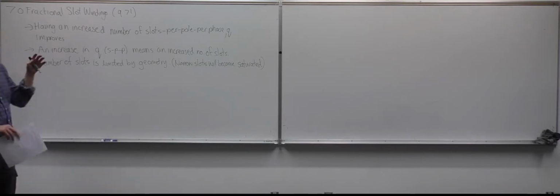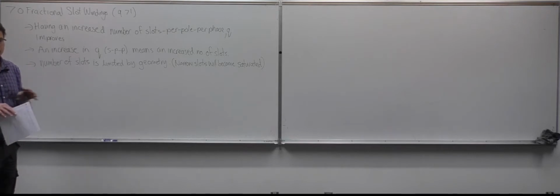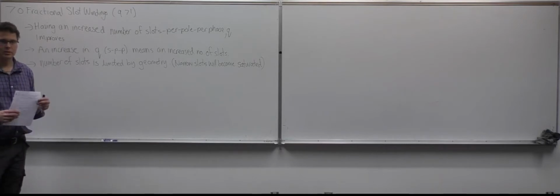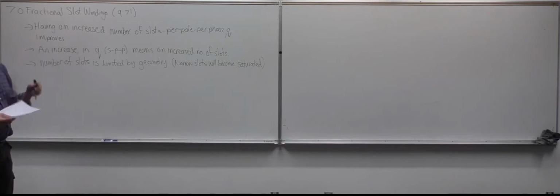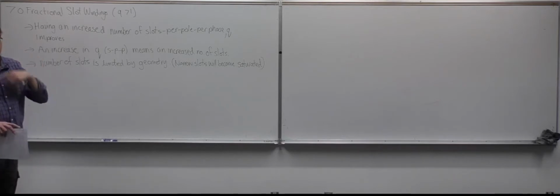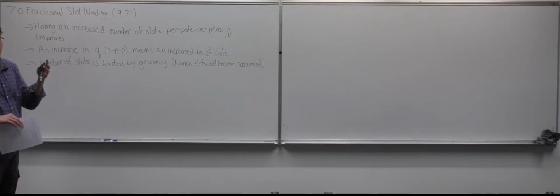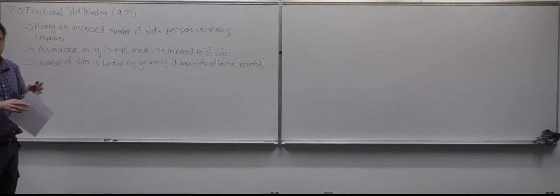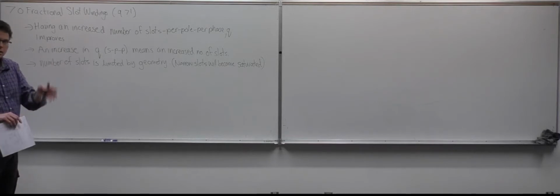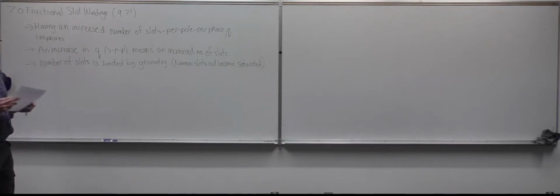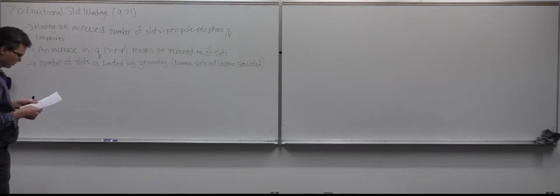So fractional slot windings allow you to widen the number of slot choices that you can use, and you can find other designs that can create better results. Because remember, the field from the stator may create, say, 7 pole pairs, but the stator slots can be a completely different number that's not necessarily related to the pole pair number by an integer. That's what fractional slot design allows you to do.